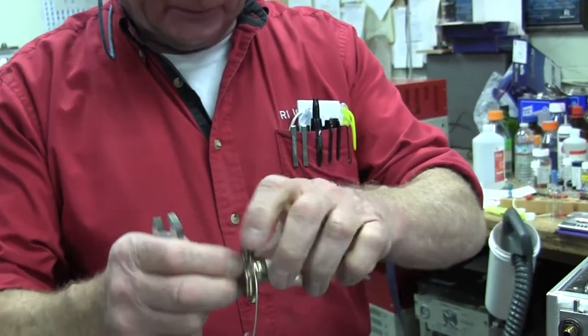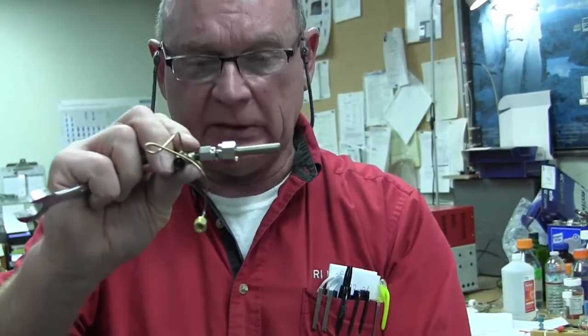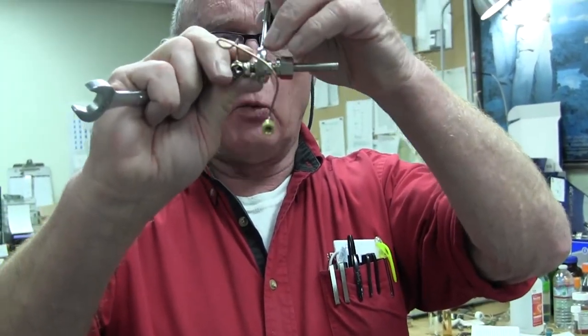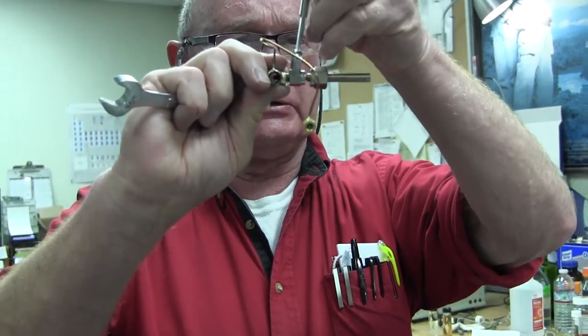When you tighten up the nut, you have to make sure not to let the tubing slip while you're tightening the nut. You might need to look at it while you're tightening it just to make sure that it's not moving.